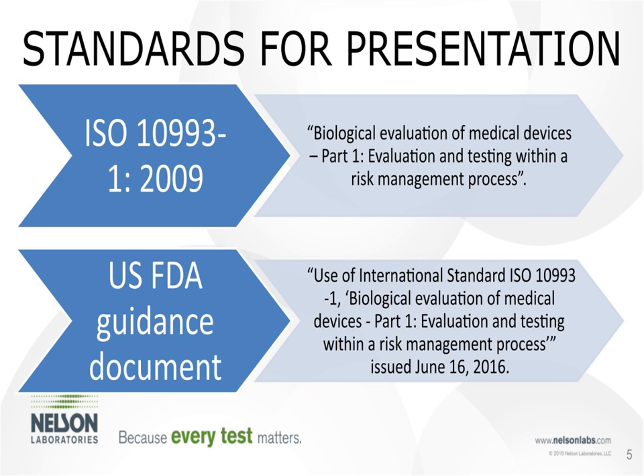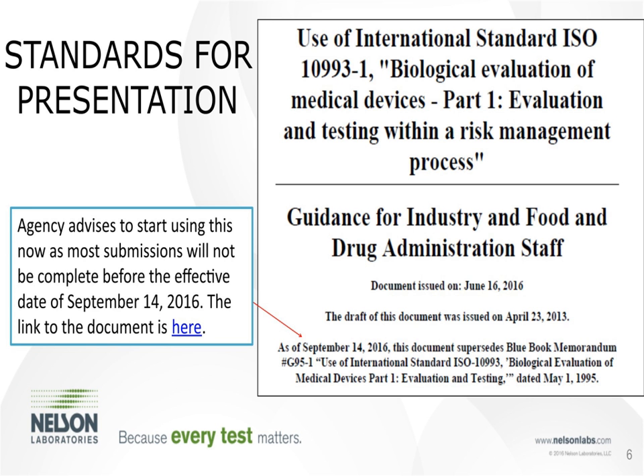The next reference is the US FDA guidance document, which is free online. A live link is on the slide, and the link is also in the public chat under Thor Rollins's entry. It's important to note that even though this was published in June, as of September 14th it will supersede the Blue Book Memorandum G95, and reviewers are already reviewing to this standard. You need to be in tune with what's going on even before changes take effect.